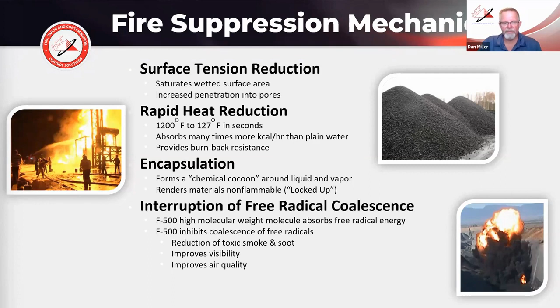Rapid heat reduction can take heat in a room from 1200 degrees to 127 degrees in a matter of just a few seconds. It absorbs many more times thousands of calories per hour than plain water. It provides excellent burn back resistance because of the features of both the wetting, the temperature reduction, and the encapsulation of carbons and hydrocarbons. Encapsulation itself forms that chemical cocoon around the liquid and the vapor and renders the materials non-flammable or locked up. And then, as we mentioned, the interruption of the coalescence of free radicals. It helps block those free radicals from coming back together and forming new compounds. So as it's applied, you see that smoke disappear immediately.